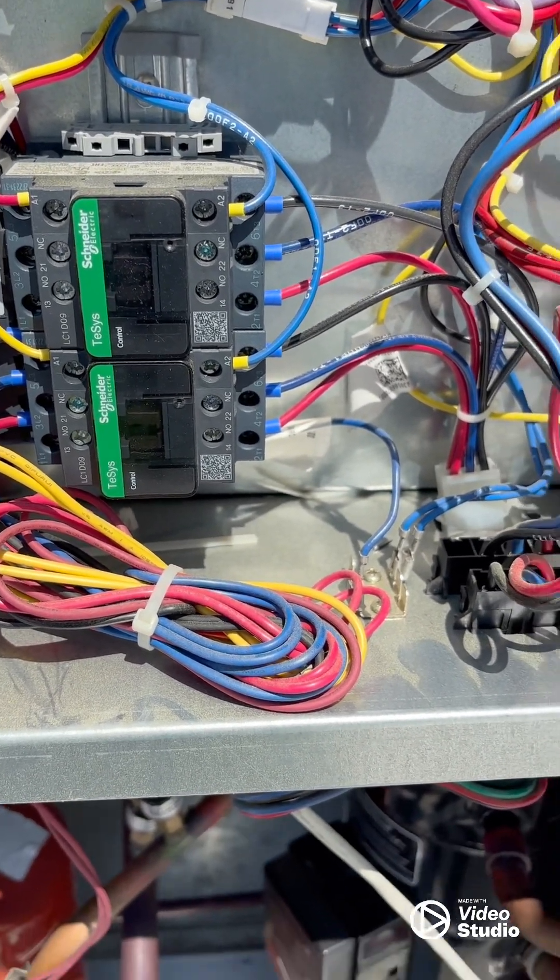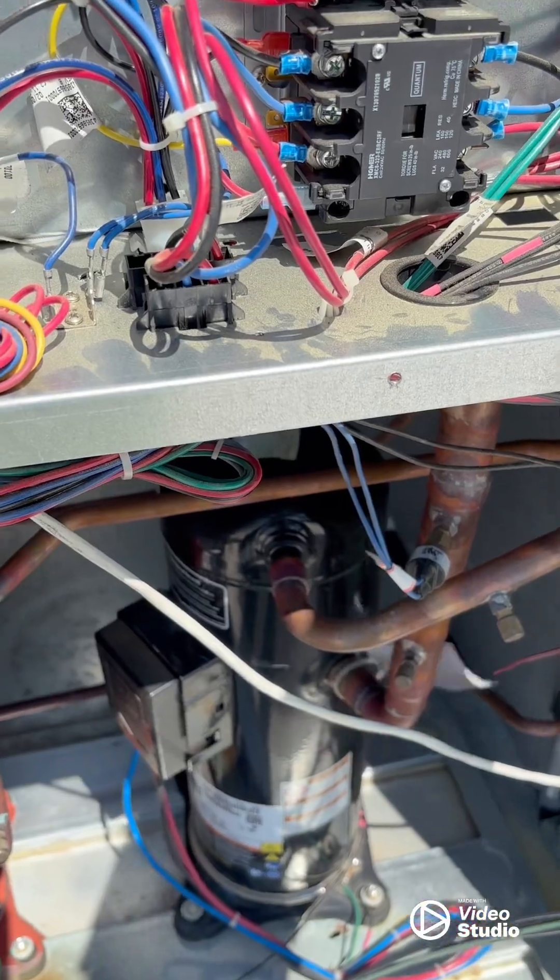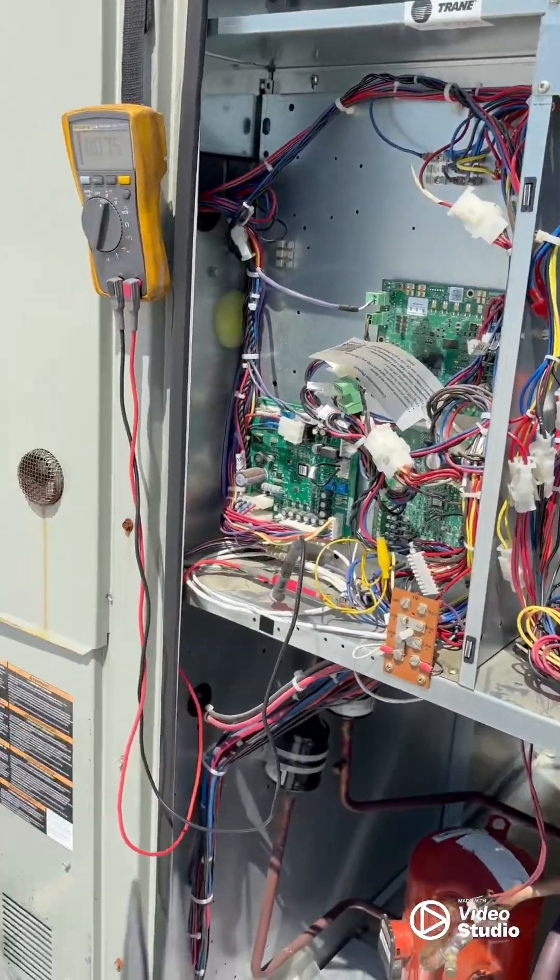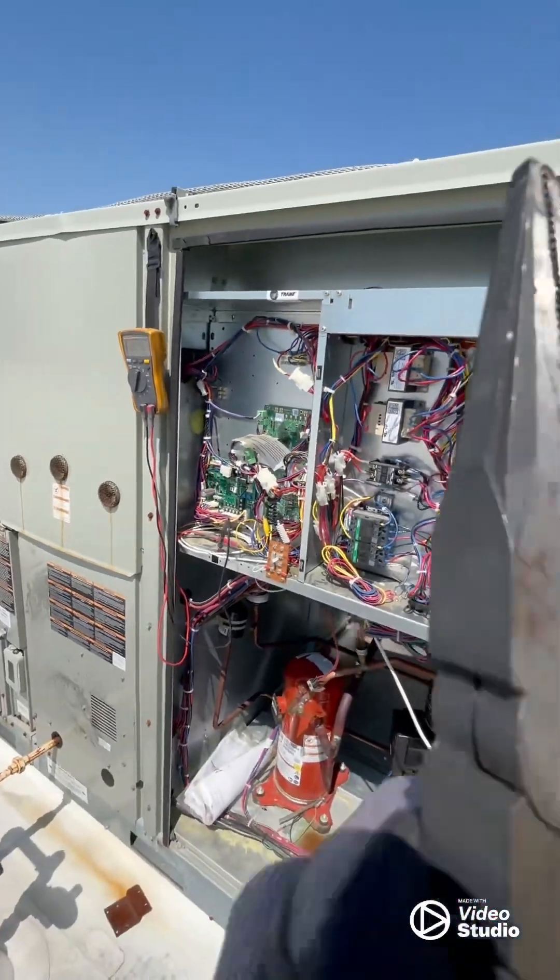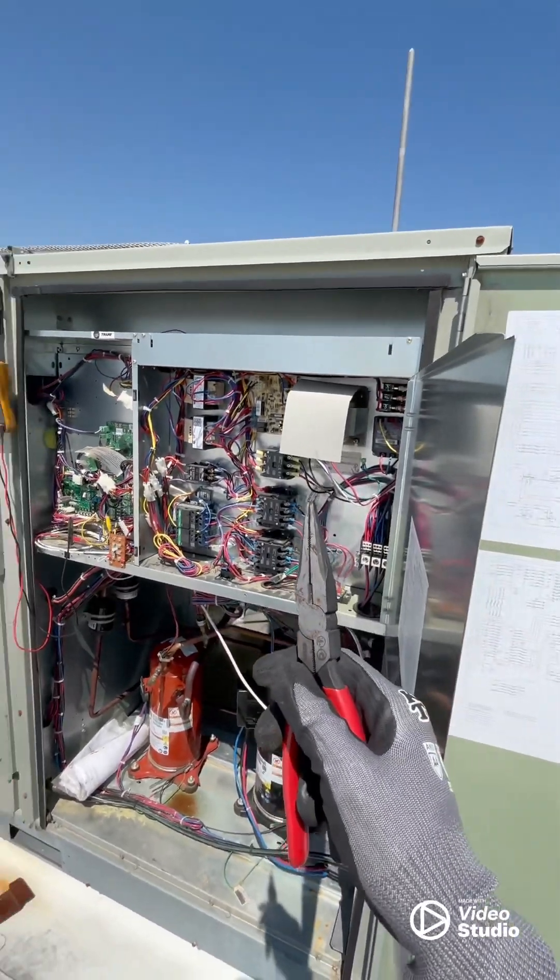See. And then stage compressor number one is going to jump on. So I got to replace the board and this unit should be back up and running.